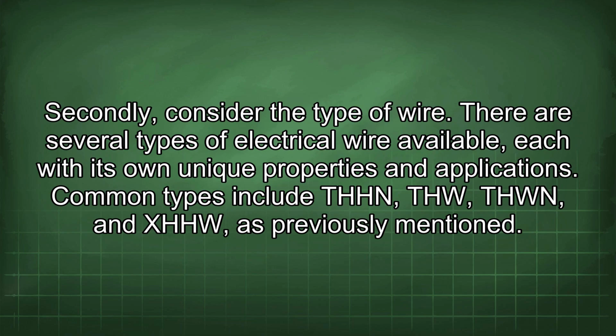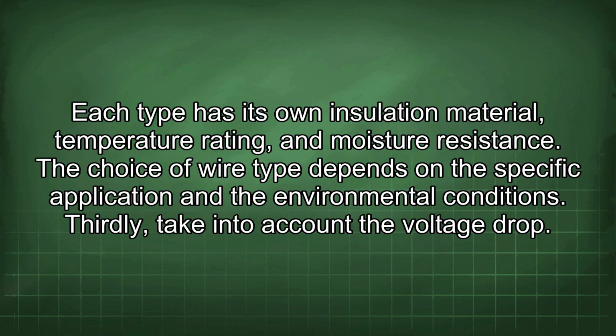There are several types of electrical wire available, each with its own unique properties and applications. Common types include THHN, THW, THWN, and XHHW, as previously mentioned. Each type has its own insulation material, temperature rating, and moisture resistance. The choice of wire type depends on the specific application and the environmental conditions.